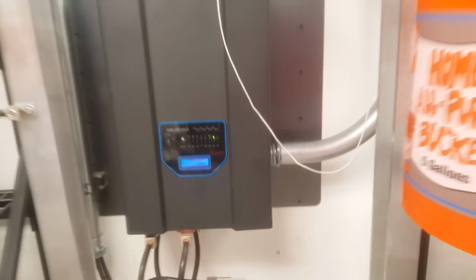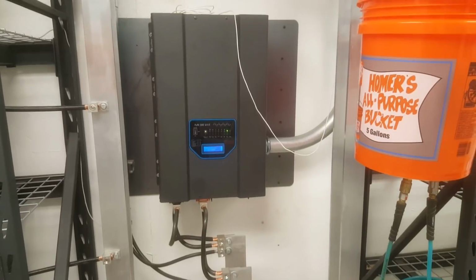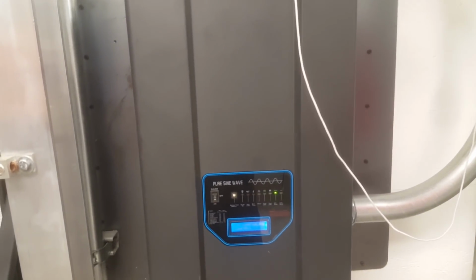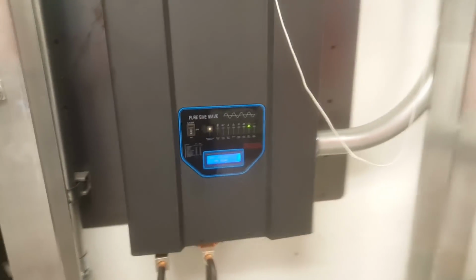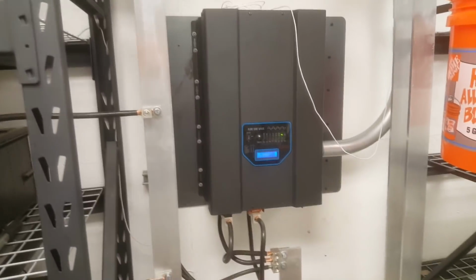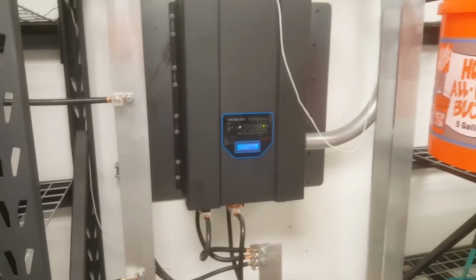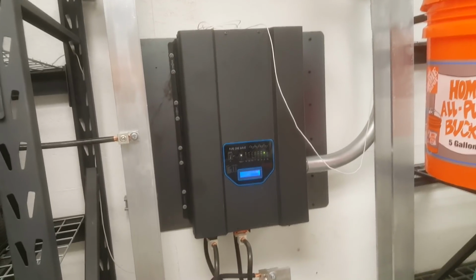From the batteries, I have my connections here, just bolted directly onto the bus bars, and here I have a Chinese-made 12,000 watt continuous, 36,000 watt peak inverter. By the way, these batteries are at 48 volts nominal voltage, and it has cooling. This inverter is very good because it's transformer based, which means it doesn't rely on diodes or transistors for its main transfer of power. This is also a battery charger capable of 120 amps at 48 volts, which pulls about 6,000 watts on the generators when it's charging the batteries.